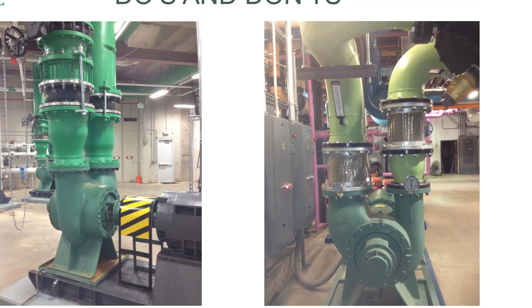Pressure gauges, you can kind of see it on this one here. They're over here as well in different locations, but nonetheless, there are tappings there. Put pressure gauges on pumps, especially on the discharge side. If there are going to be issues and you start calling people or you go to the job site, I'm sure most of the details in your pump packages and MEP drawings show pressure gauges. But if they don't, put them in there. Definitely on the discharge. If you can also get one on the suction side, I know maybe it costs too much, blah blah blah. But really, that differential is proportional to the total head for the pump. It's a lot easier to diagnose problems when you have that.